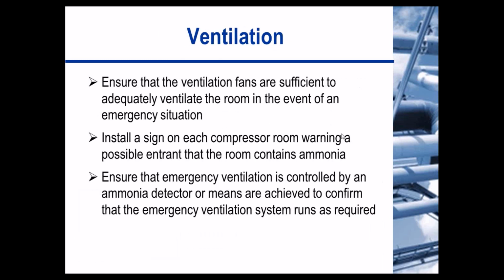So let's talk a little bit about ventilation. When we look at ventilation, we want to ensure that the fans are sufficient to adequately ventilate a room in case of an emergency situation. Just having fans may not be enough. Knowing how much it would clear is a pretty important thing. Also, install a sign on each compressor room warning an entrant that the room contains ammonia. And also ensure that emergency ventilation is controlled by an ammonia detector, or means are achieved to confirm that emergency ventilation runs as required.